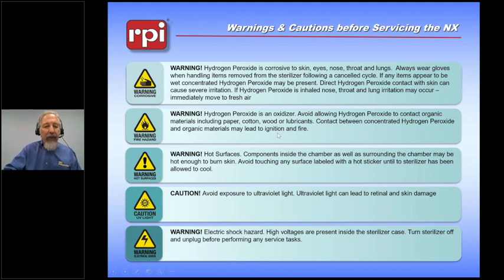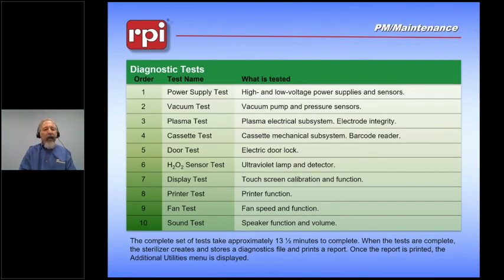Okay, again, we talk about hydrogen peroxide. There is a UV system, and of course, whenever you're working on electronics, be very careful to avoid getting electrical shocks. So, diagnostics. This machine has built-in diagnostics that you can run through a service password. This is what's included within the diagnostics, all the various systems that are checked. This process takes about 13 minutes to complete, and when it's done, it will print out a sheet that gives you the results of all of these tests.